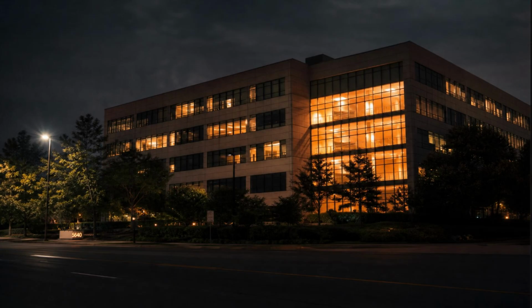The goal of an emergency power system is a simple one, if you say it plainly. When the normal source of electricity becomes unavailable, something must step in and keep the most critical functions of the building running. The lighting in the stairwells, the pumps that supply water to sprinkler systems, the equipment in operating rooms, the controls for smoke exhaust fans, the things that, in a moment of disruption, matter most.